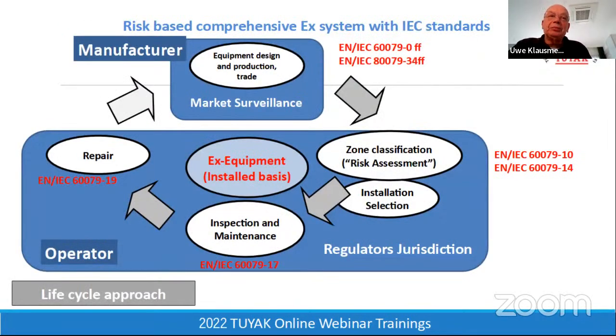Okay, coming to the comprehensive concept of the Ex system. This is to show you, let's start with the equipment which has to be designed, and which are the components you can find in such a factory: lighting, motors, and so on. They have to be designed according to IEC standards. The IEC standards, this is the source. As soon as you see, okay, this is EN, I have to apply a European norm, then you have to be aware that the European norm is identical to the IEC norm.